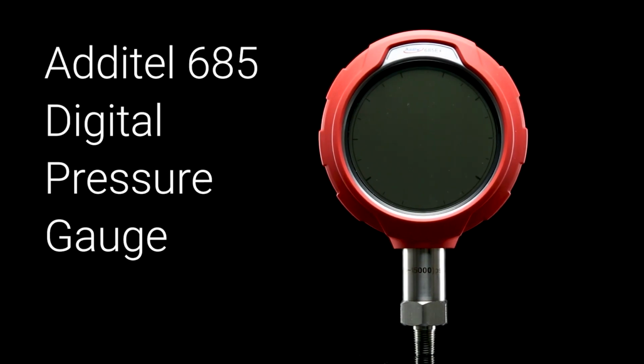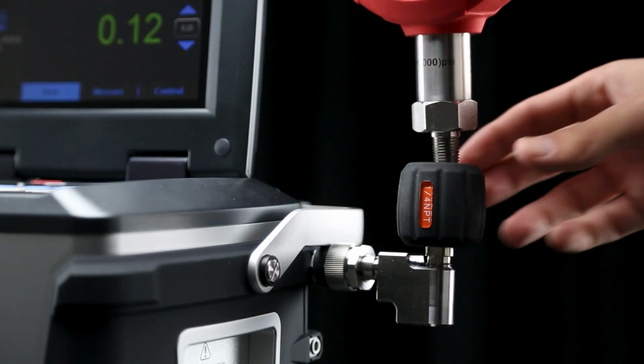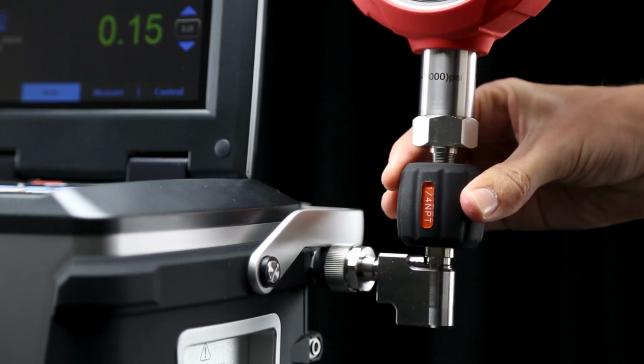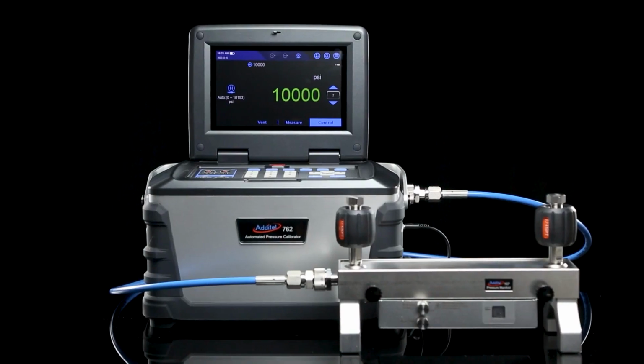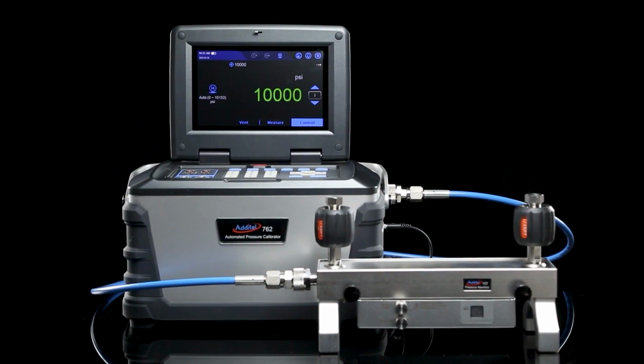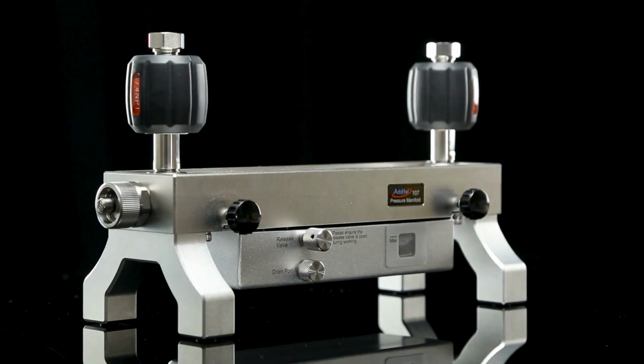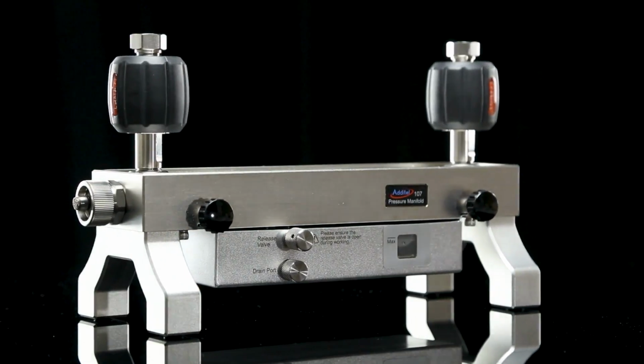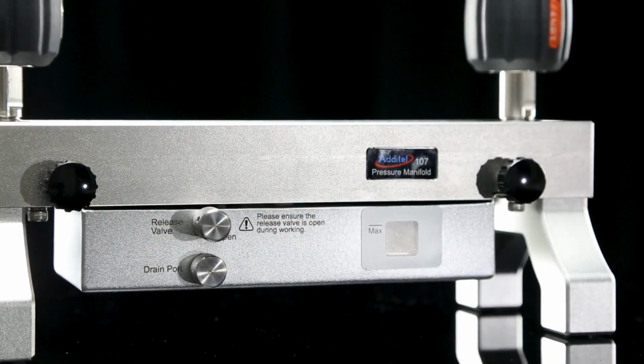In this demonstration, we'll calibrate an Additel 685 digital pressure gauge, which will be attached directly to the 762 by hand tightening the quick connect fitting on the right-hand side of the device. If you want to calibrate multiple devices at a time, you must use the ADT 107 manifold that communicates with the 762 directly to prevent oil contamination.